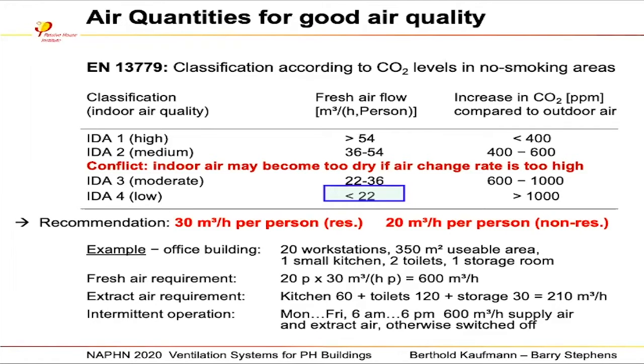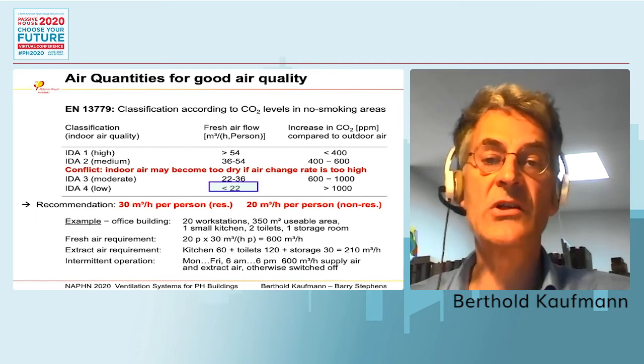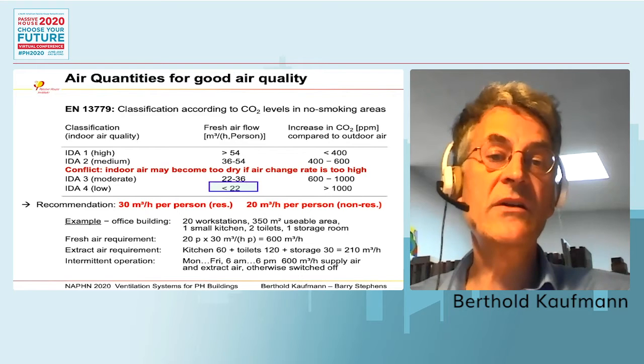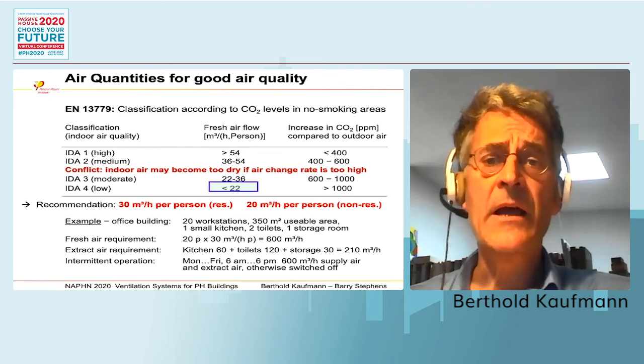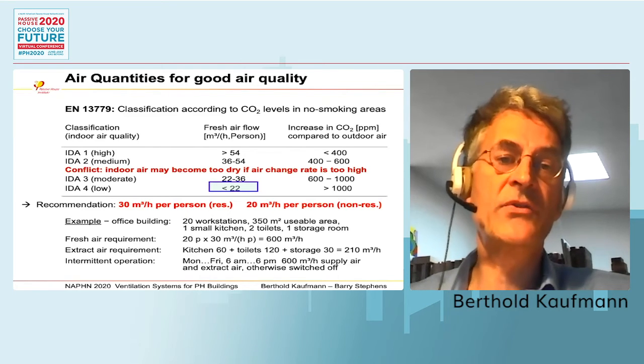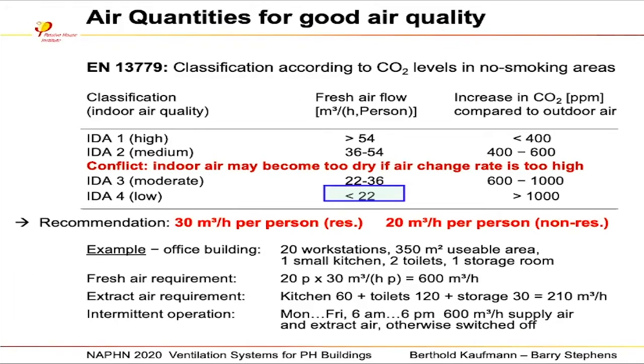There are some quantities by numbers to get typical air quality inside buildings. You see the international standard denotes 4 quality levels: indoor air quality 1, 2, 3, and 4. IDA stands for indoor air quality. The high and medium levels are for technical issues. So if you have a lab or a medical room, this might be quite good, but it's not suitable for residential and for office use. So we recommend to go down to IDA 3, or if you go for meeting rooms, for schools and so on, you might even go lower to IDA 4.